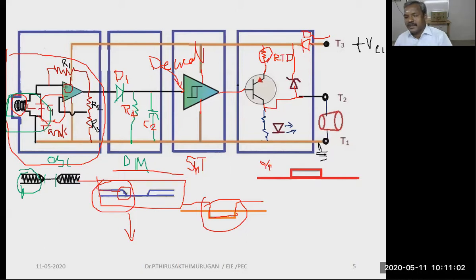When the object is nearing the sensor head, suppose we set the set point. The moment the object reaches that distance, the hooter will generate sound. That is the operation of the inductive proximity pickup. It will generate sound, or you can connect any automatic switch-off or shutdown system here, whatever you want to connect across T1 and T2. This is for the output circuit.